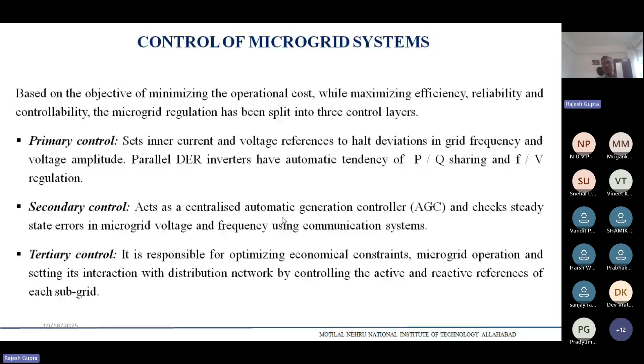And tertiary is the almost outer level, governed by optimization, economics, and other outside world interaction. Who is doing what, whether to switch to islanded mode, whether to switch to grid connected mode. So that's the tertiary level. This is the hierarchical way: primary, then secondary, and then tertiary. Under primary you can see protection, power sharing, voltage frequency. Secondary: droop control, active, reactive, grid synchronization. And tertiary: market participation, interconnection, coordination of multiple microgrids, optimization. So these are the various levels, and it is a hierarchy.